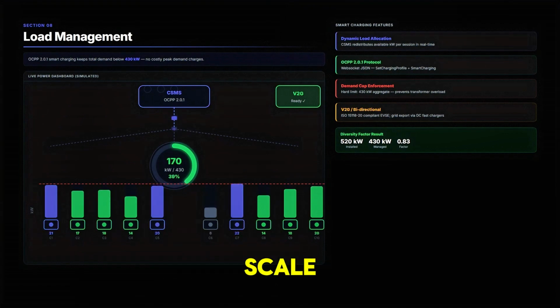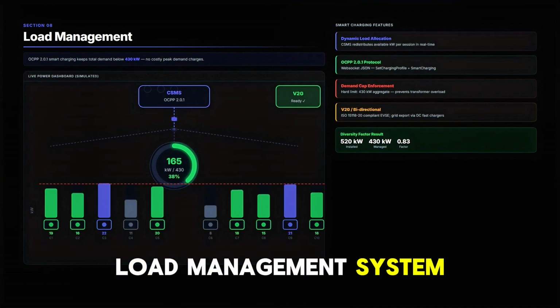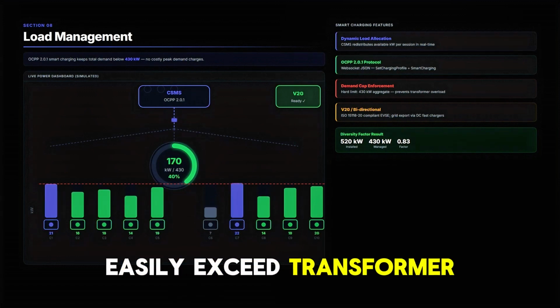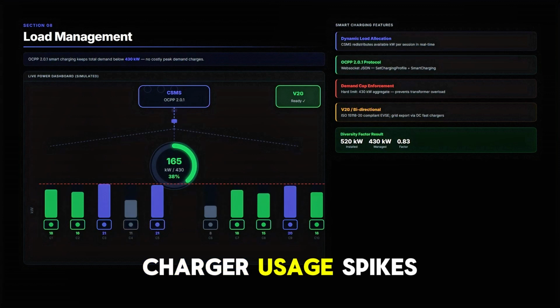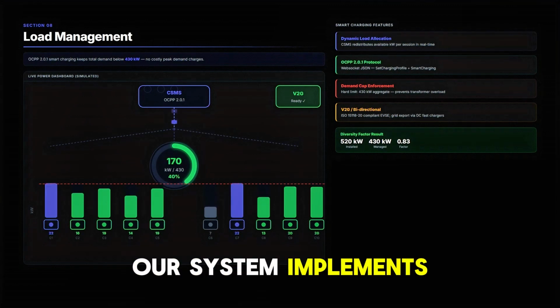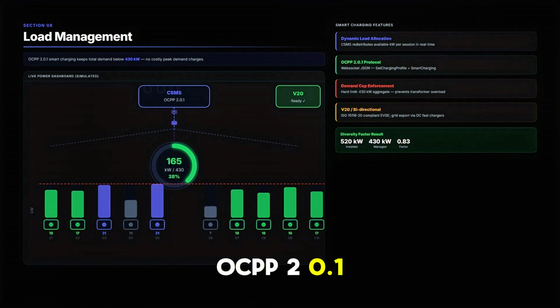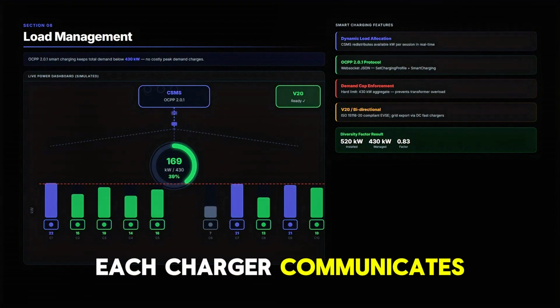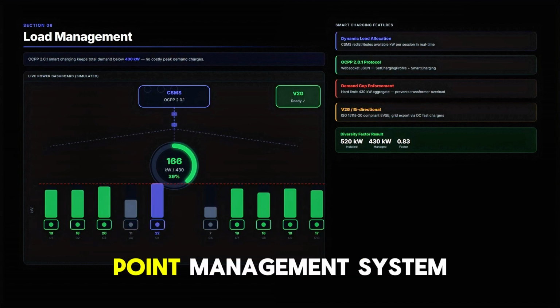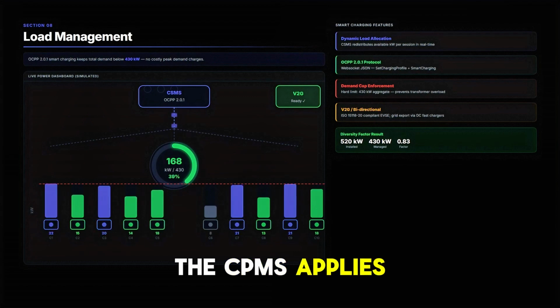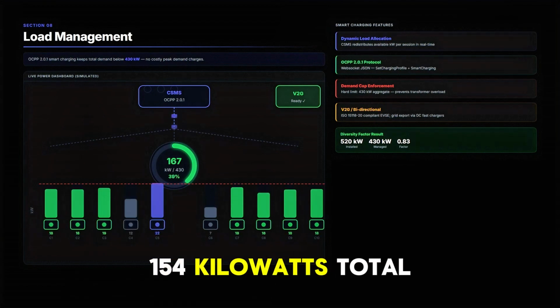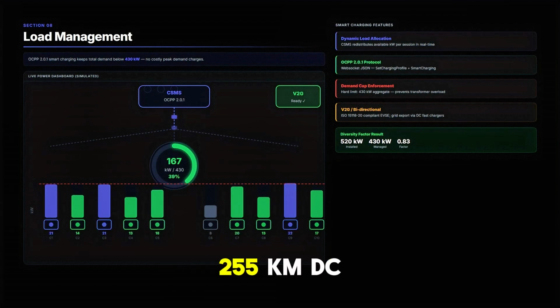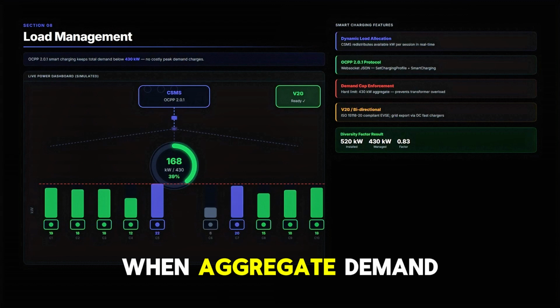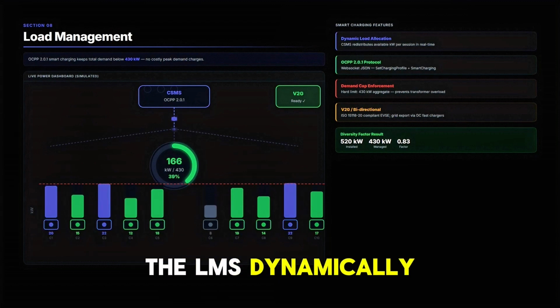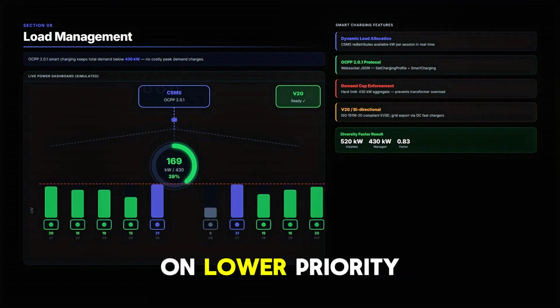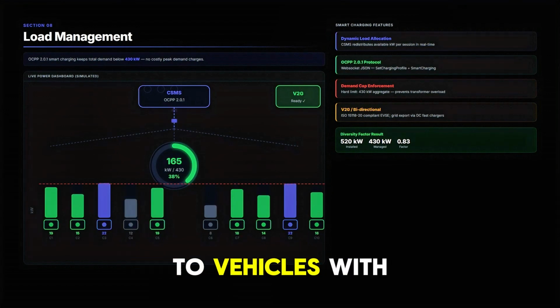Load management. At this scale, it is not optional. Without a load management system, peak demand can easily exceed transformer capacity, particularly if EV charger usage spikes in the morning or evening peak. Our system implements OCPP 2.0.1, the Open Charge Point Protocol. Each charger communicates real-time power draw to the charge point management system. The CPMS applies our demand limits: 154 kilowatts total for AC chargers, 255 kilowatts for DC. When aggregate demand approaches the cap, the LMS dynamically reallocates power, reducing charge rate on lower priority vehicles and redirecting capacity to vehicles with greater need.